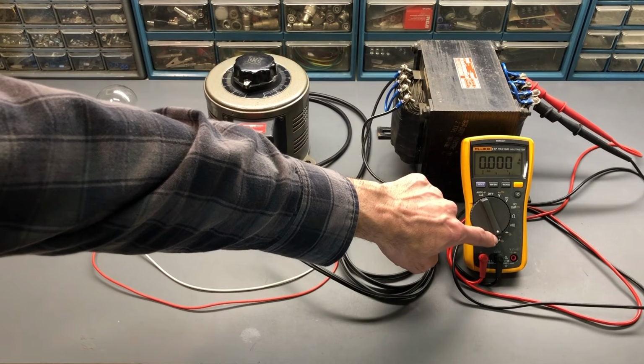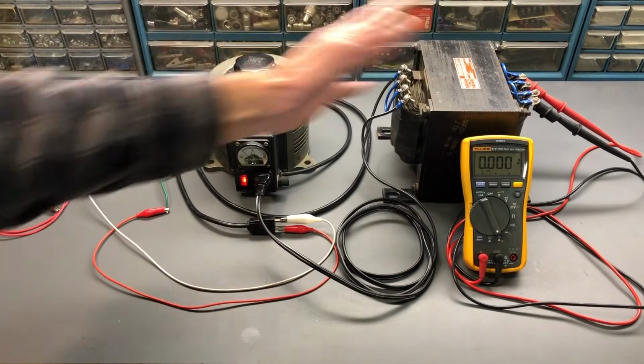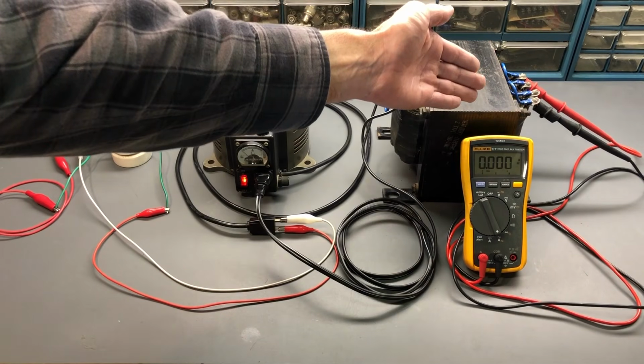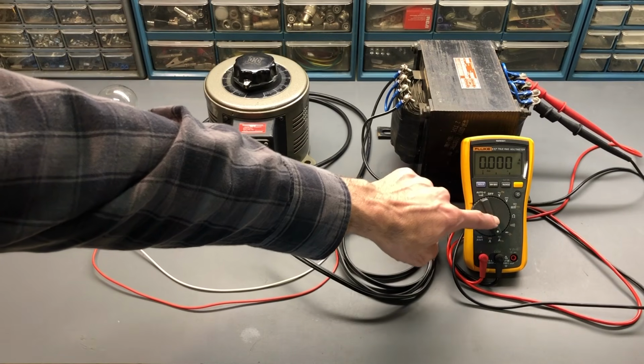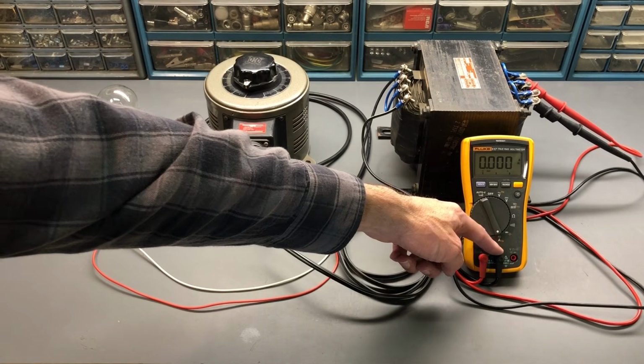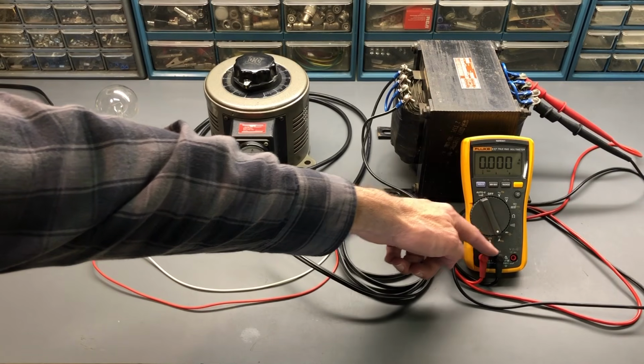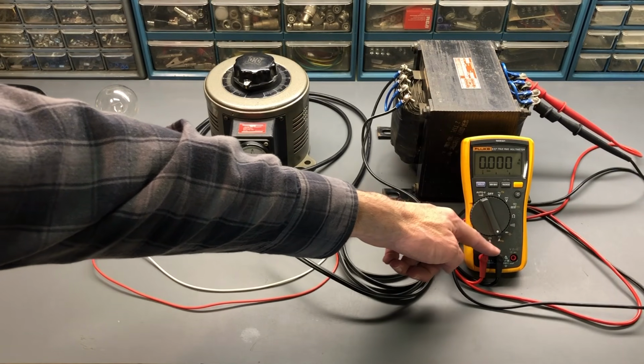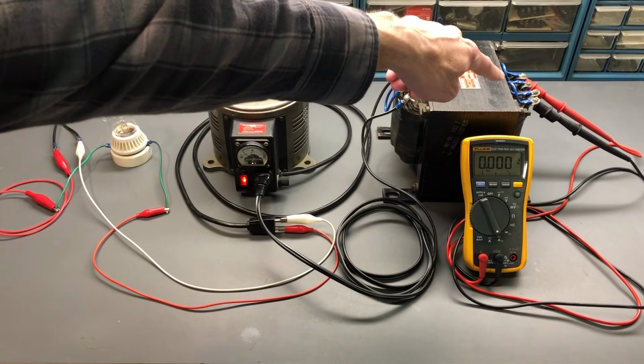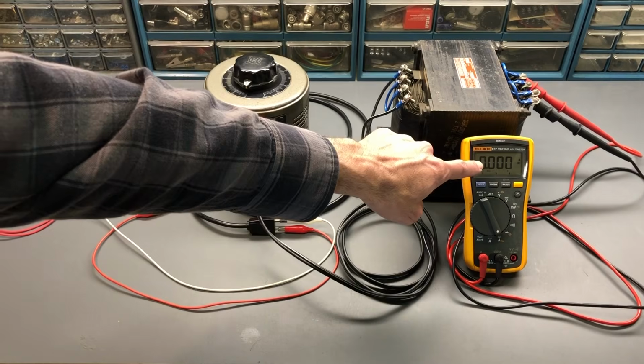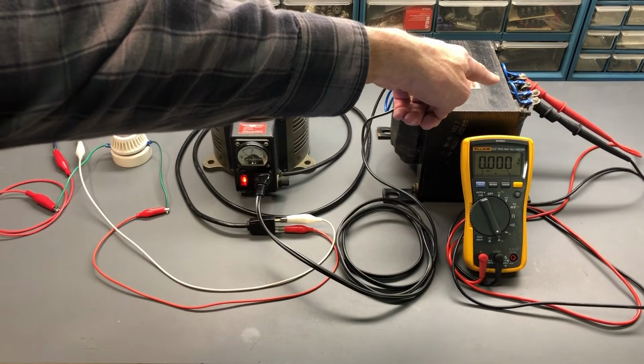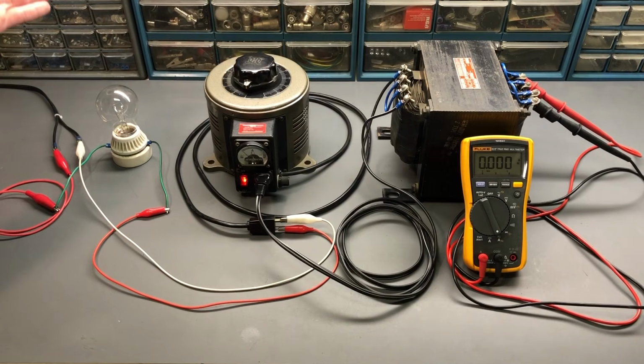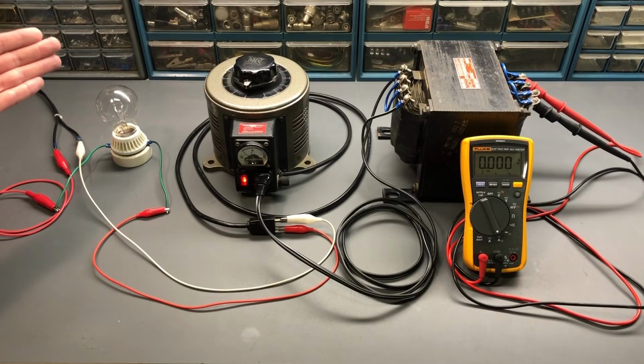It's set to AC current or AC amps, and it's connected across the secondary, in this example, of the isolation transformer. This meter is acting like a direct short because in the AC current or amps position, there's an internal shunt between these two test leads, so there's a very low resistance. So this is acting like a short circuit across the transformer right now, and it will indicate the current that is able to flow through the secondary windings that would be limited by the incandescent lamp, because that's the whole purpose of this circuit and this setup, is to have current limited to a very safe value should a short circuit occur. Normally when you're using it, there would not be a short circuit over here.